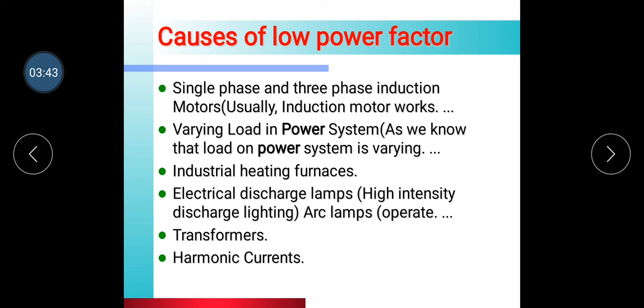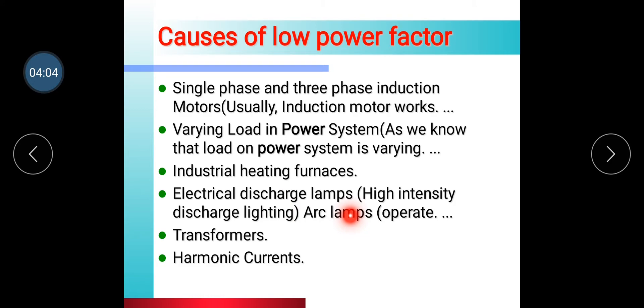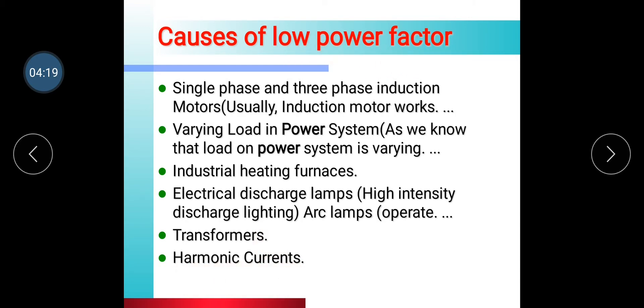Causes of low power factor include: single phase and three phase induction motors; lightly loaded power systems where the load is too low; industrial heating furnaces; electrical discharge lamps, high intensity discharge lamps, and arc lamps; transformers not operating properly; and harmonic currents.